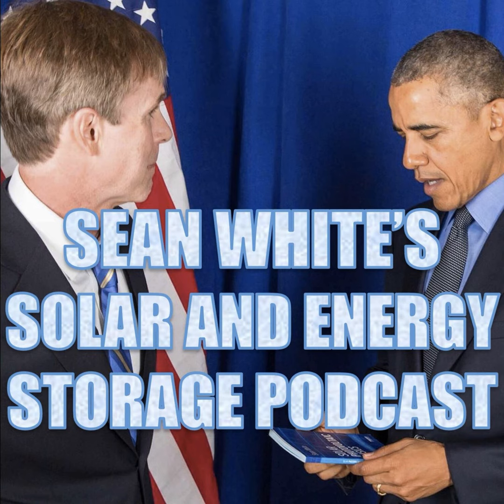Plus, PV's been around for quite a while, and a lot of us know how to define PV currents. And we're talking wild PV there. That's PV that is a silicon crystal in the sun that turns light into electricity. And since we can't have a dimmer switch for the sun, we're a little bit extra conservative, and we have this 125% of short circuit rule that we use for these PV source circuits.